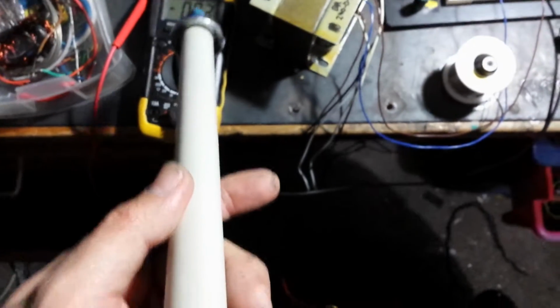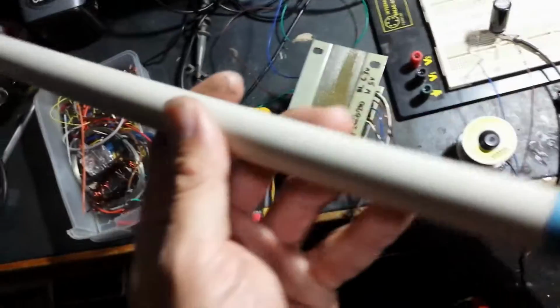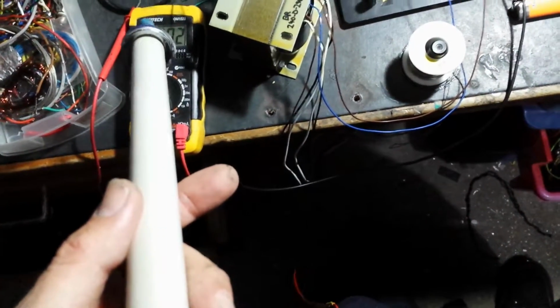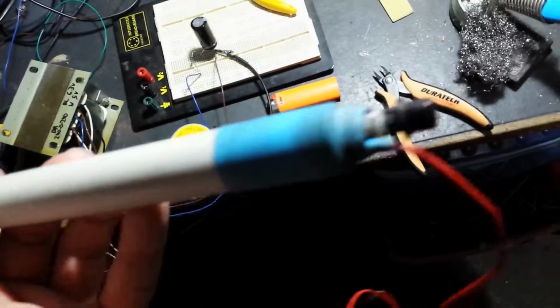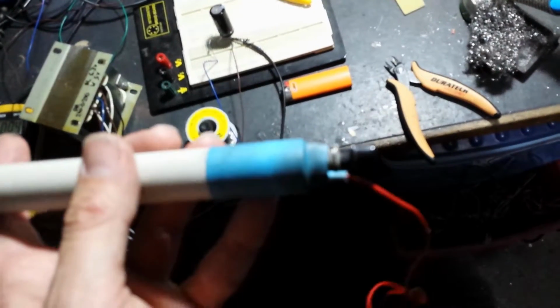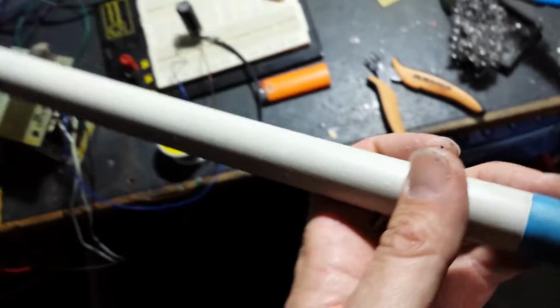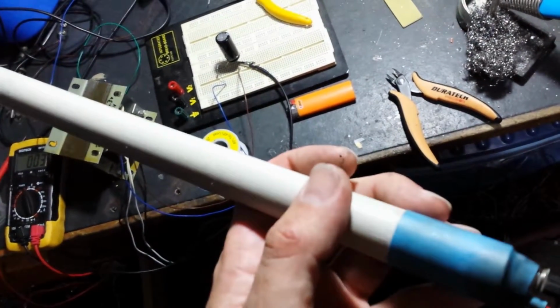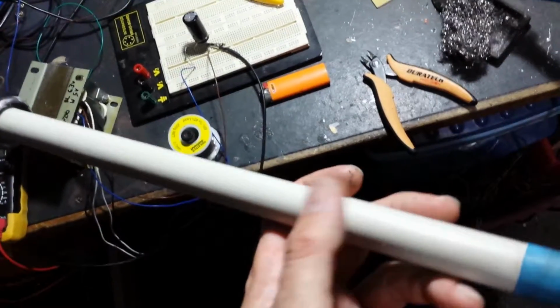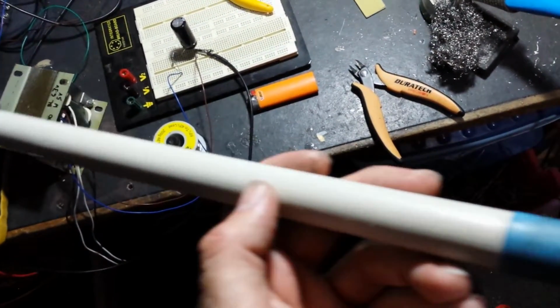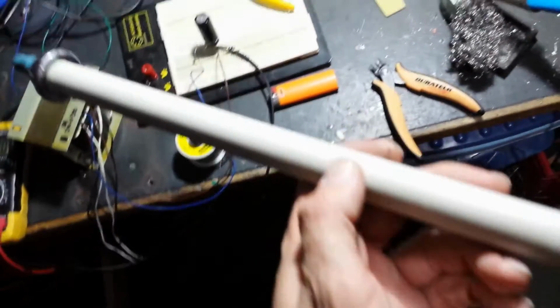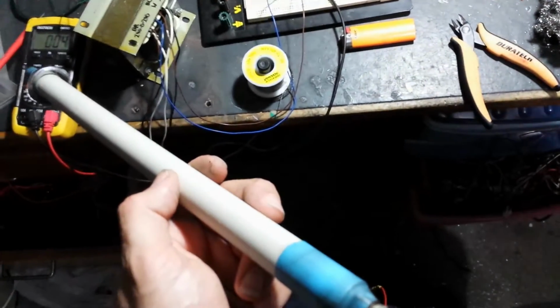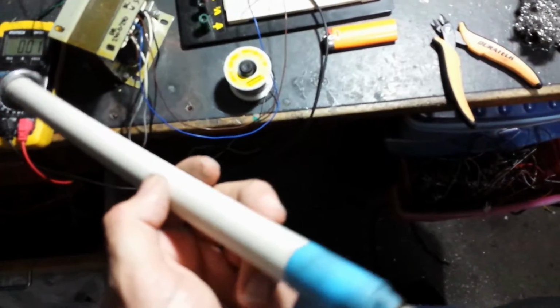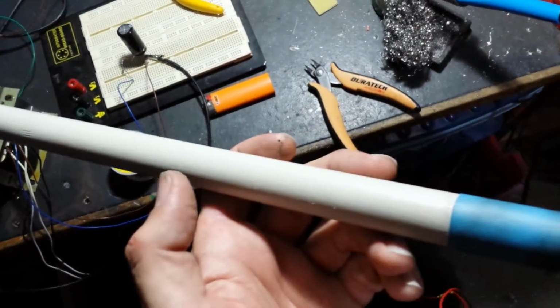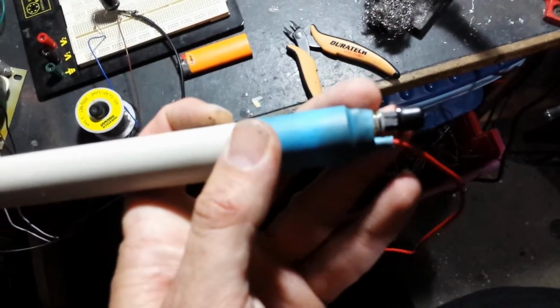So say for instance I'm reading 5,000 volts with this probe, I'll be getting 50 volts instead of 5,000 volts. I've also added another 10 meg ohm resistors, and I've added a switch here so I can divide the voltage reading by 200. So if I'm reading extremely high voltages in the tens of thousands of volts, I can get the reading divided by 200. Say I'm reading 20,000 volts, it'll come up as 100 volts instead of 200 volts if I had it set to divide by 100.